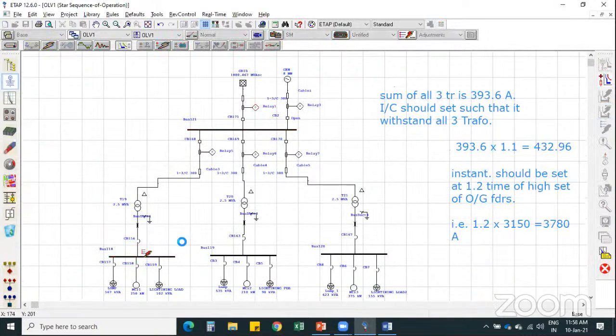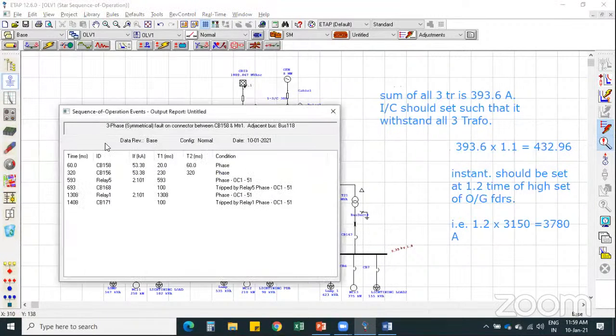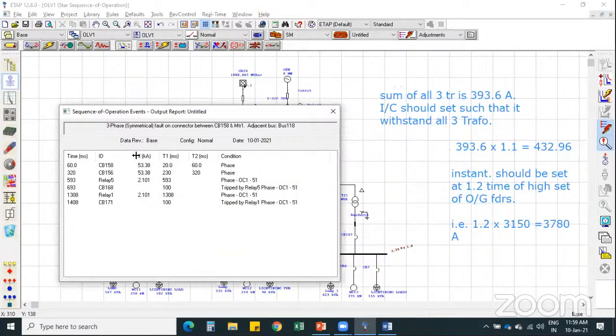Now let's see the coordination and the sequence of operation. If this fails to operate, then this will operate. If this fails to operate, then this relay will operate. Similarly, if a fault occurs in this downstream network, the particular section will operate first. If this fails to operate, then this will operate, and if this fails, then the primary side of the transformer will operate. Here we can see the time of operation and at what particular value the relays trip.